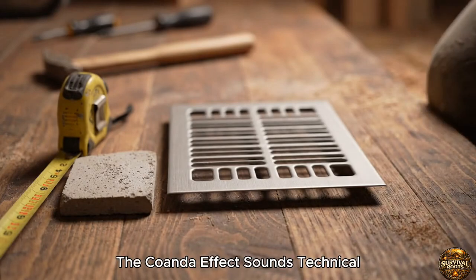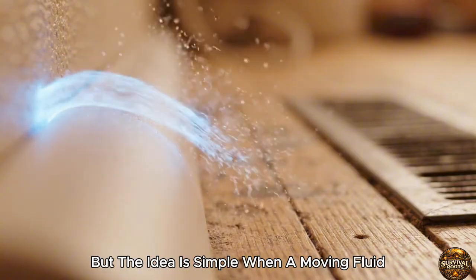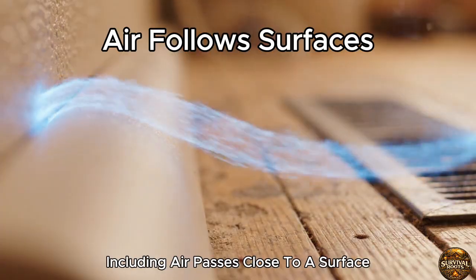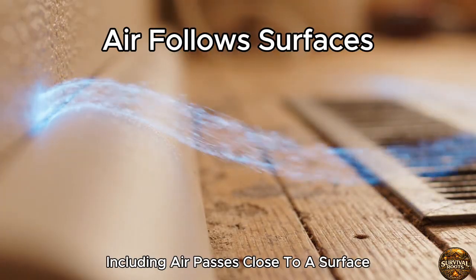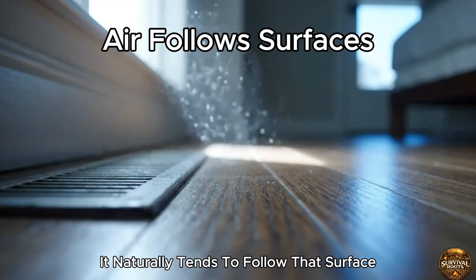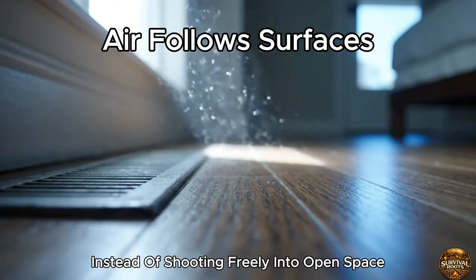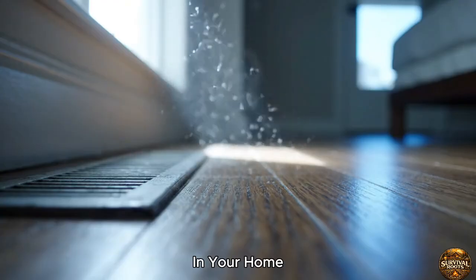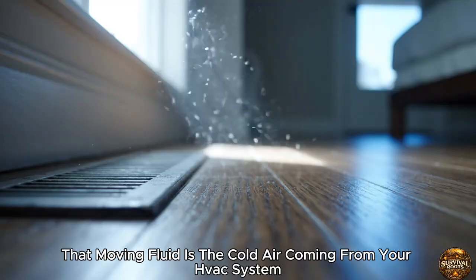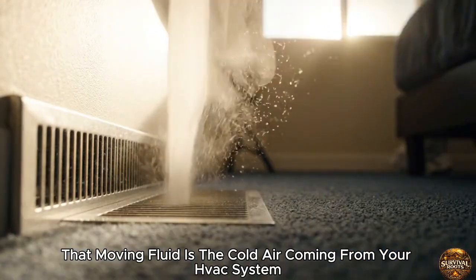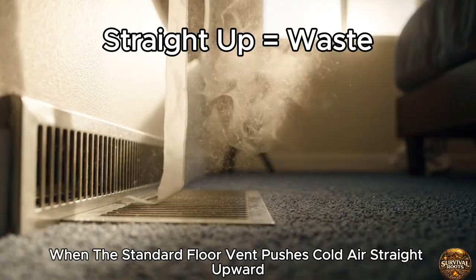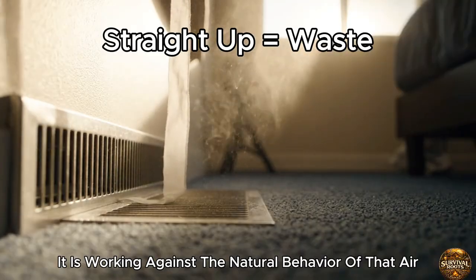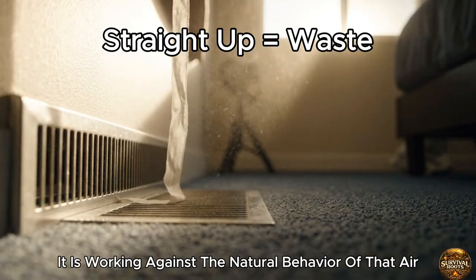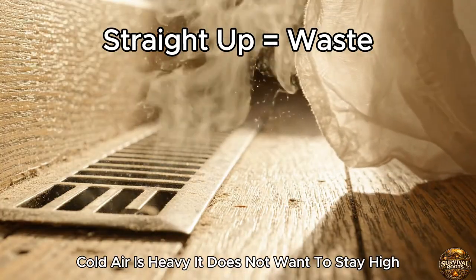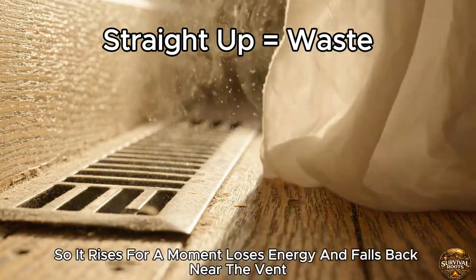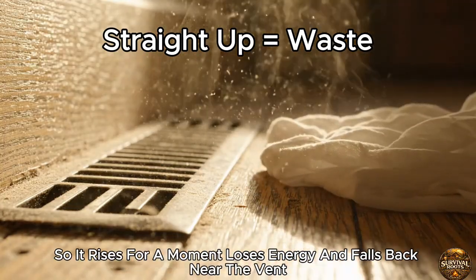The Coanda effect sounds technical, but the idea is simple. When a moving fluid, including air, passes close to a surface, it naturally tends to follow that surface instead of shooting freely into open space. In your home, that moving fluid is the cold air coming from your HVAC system. When the standard floor vent pushes cold air straight upward, it is working against the natural behavior of that air. Cold air is heavy. It does not want to stay high, so it rises for a moment, loses energy, and falls back near the vent.